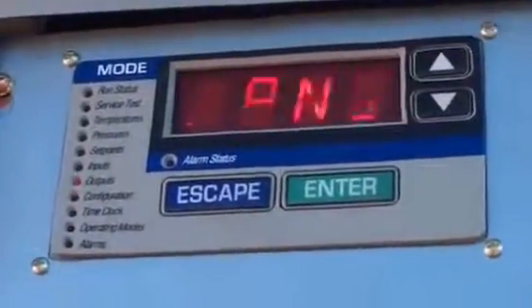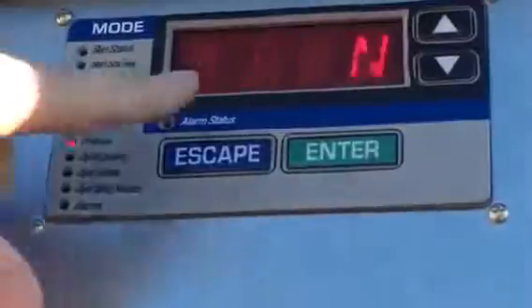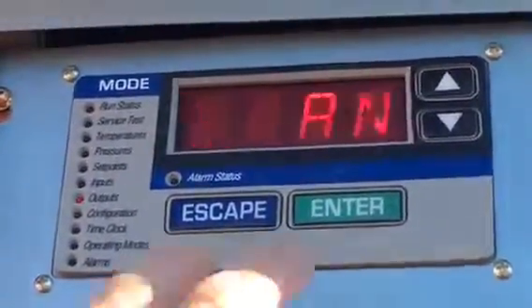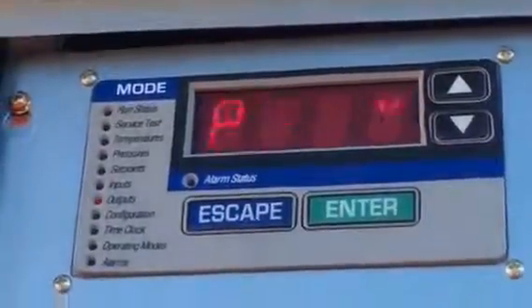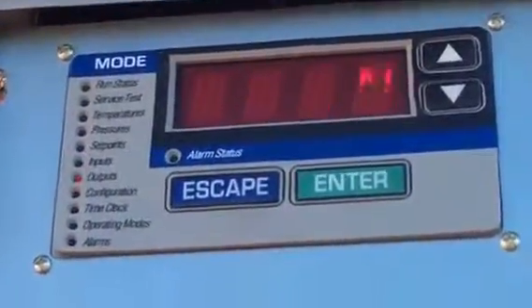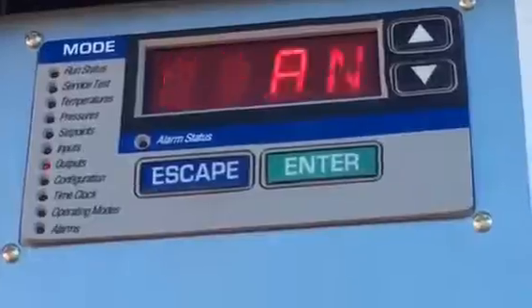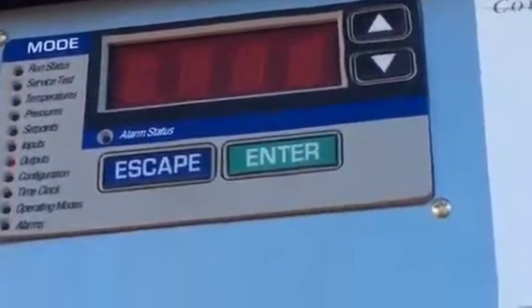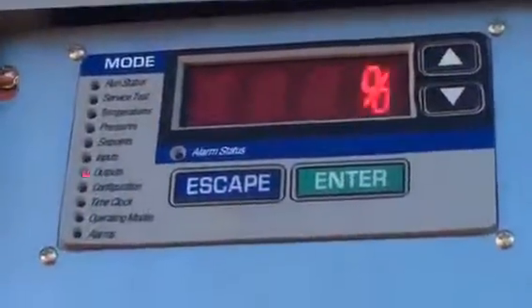If I back out, let's go to outputs, fans. I can see what fans are in outputs. What is S.FAN? Supply fan. I don't know. Why don't we hit escape and enter? VAV unit with a drive, so I close a relay to power the drive. That doesn't mean my fan runs yet. I still need to give it a speed command, so there's another step involved about a speed command. And then my next step is the S.VFD, which would be what? Speed for the VFD, and it shows me 33%, 32.5%. So they're almost equal.